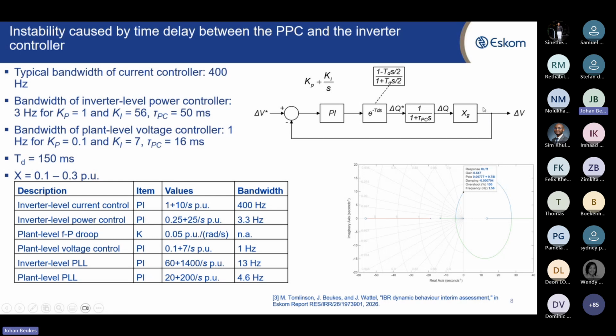What's important here is that even if you have a BESS that's supposed to support the grid in grid following mode—just to come back to grid following versus grid forming—these are all grid following examples, meaning a current source is injected into the grid, relying on a control system to give a current reference. A grid forming inverter acts as a voltage source instead, so it spontaneously delivers its current into the grid.